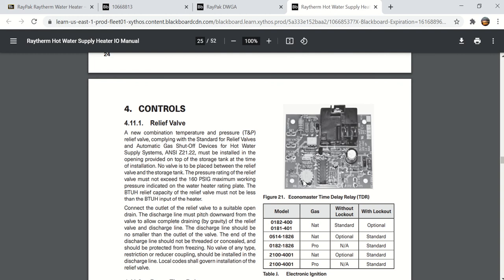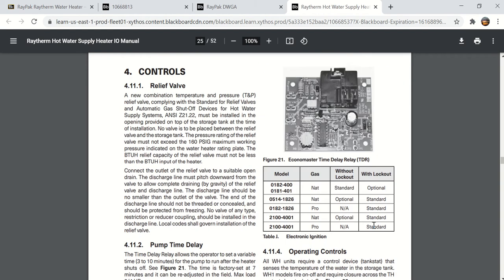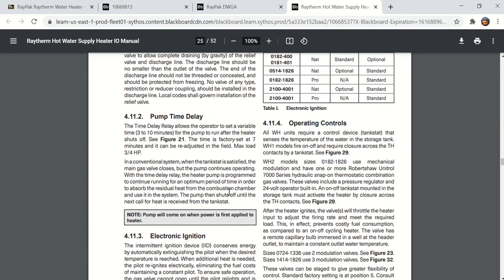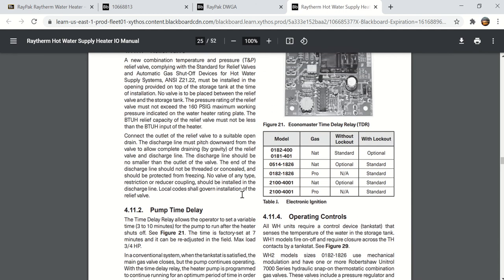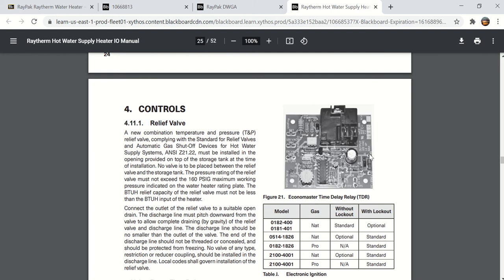And it has a little dial here that I believe, from what it says right here, the time delay relay allows you to set the delay off time from 3 to 10 minutes. Factory set at 7, with a max load of 3/4 horsepower, which is for the pump. But a time delay relay would do the same thing as this. I don't know that you always would have to buy one from RayPak, but that's really all a solid state economaster is: an off delay type relay that keeps the pump running for 7 minutes after the burner shuts off.